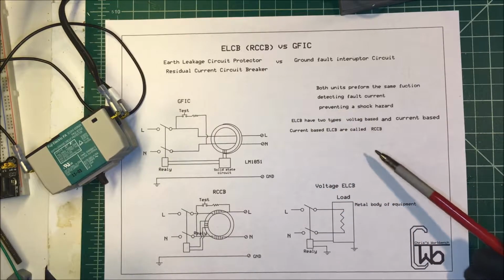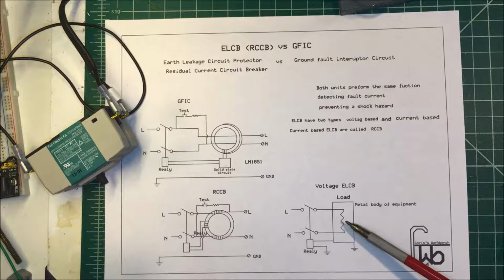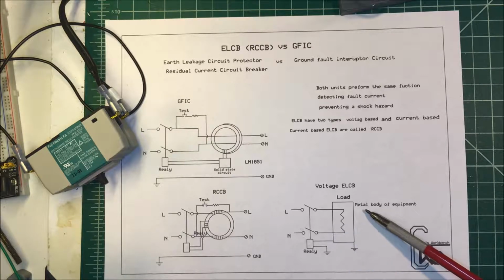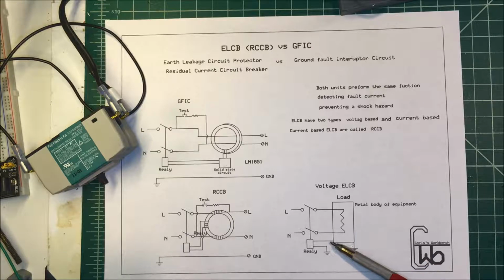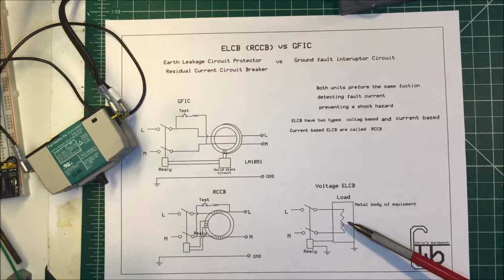The voltage ones aren't very common, but they were very simple. What they would do is just take a line off of the metal body of your equipment here and go back to the relay inside the circuit breaker, and then from there they would go to ground. And if it detected any voltage going to ground, it would trip the circuit breaker, opening up the load there.